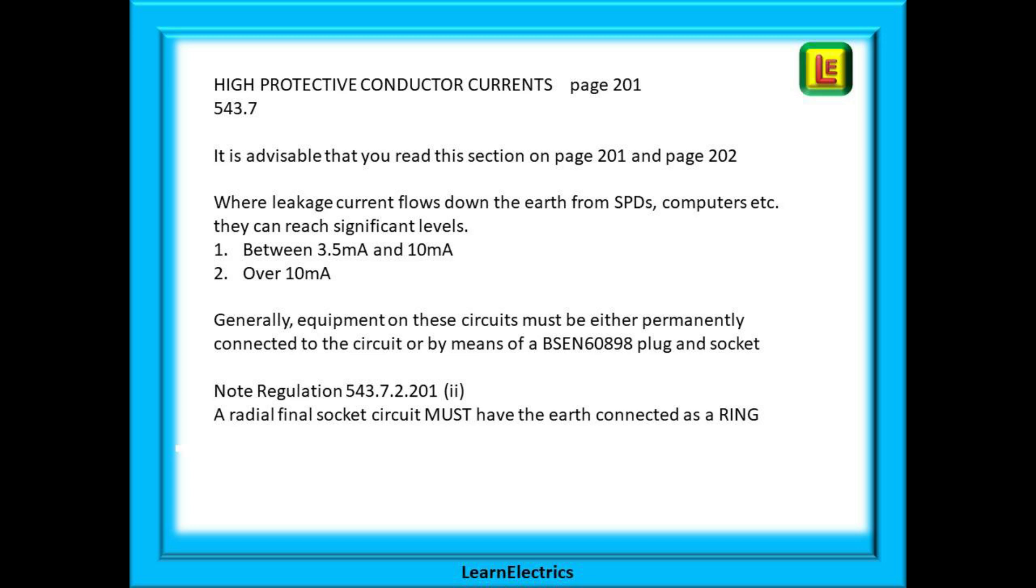The section on high protective conductor currents on page 201 is also popular for an exam question. Please take the time to read this section on page 201 and page 202. It tells us that where leakage current flows down the earth conductor from SPDs, computers etc. they can reach significant levels and they are broken down into two different areas. Those between 3.5 milliamps and 10 milliamps and those over 10 milliamps.